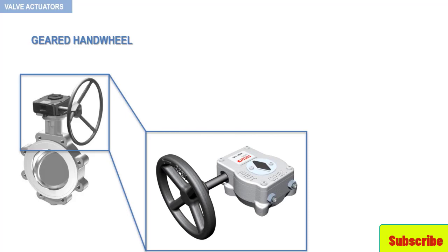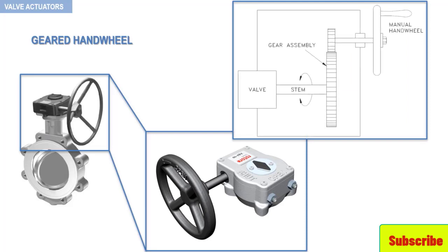And here you can see a 2D cross-sectional view of this gear head. As you can see from the figure, a special wrench or hand wheel attached to the pinion shaft permits the operator to operate the valve, when two operators might be needed without the gear advantage. Because several turns of the pinion are necessary to produce one turn of the valve stem, the operating time of large valves is exceptionally long. The use of portable air motors connected to the pinion shaft decreases the valve operating time.